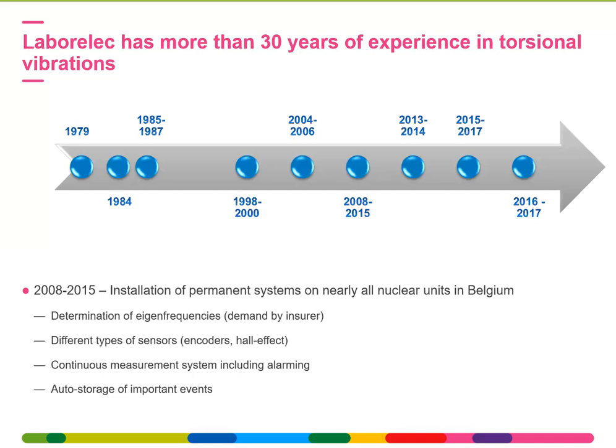Permanent systems have already been installed on nearly all nuclear units in Belgium. This was on the demand of the insurer, with the focus on determination of the eigenfrequencies. They used different types of sensors, encoders, Hall effect, typically 2 to 3 on the shaft line. And it's a continuous measurement system, including alarming and auto storage of important events.